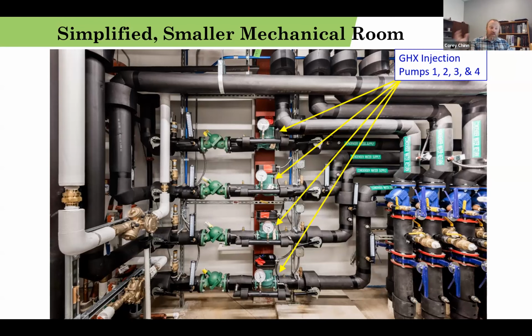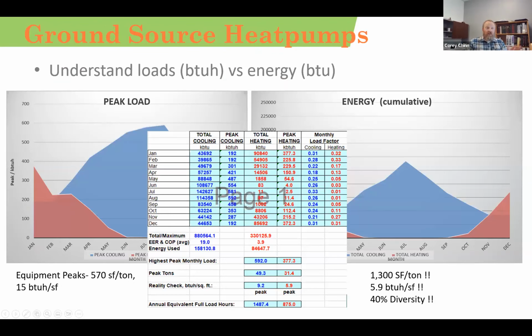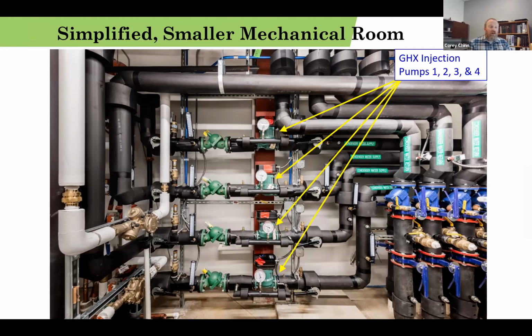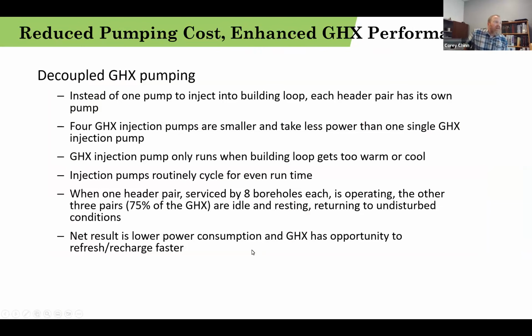So our distribution pumps, our secondary pumps that do the building distribution, are much larger. There are two pumps, and our ground loop pumps are decoupled because of that disparity that you see between our peak load and the total amount of energy that we need. So very important to understand our loads versus our energy. When I was a young engineer, I always said you can't use your load calcs for your energy model. As I got involved in geothermal, it blew my mind. And now I say you should be using your load calcs for your energy modeling, because accurate loads can do both.